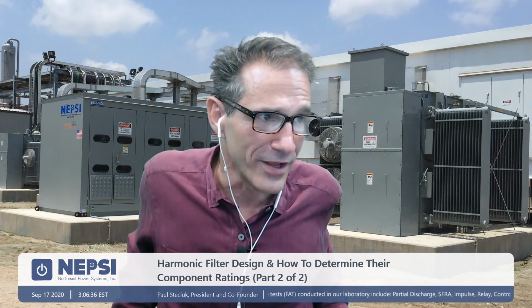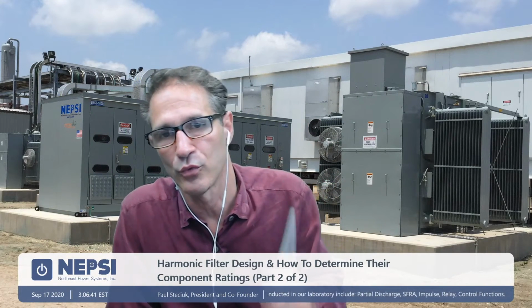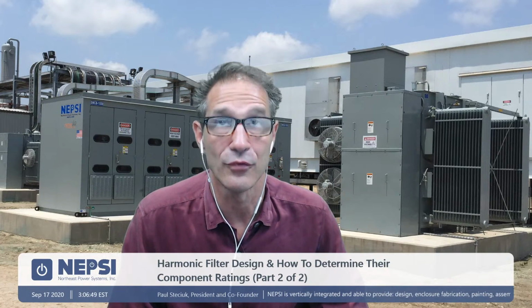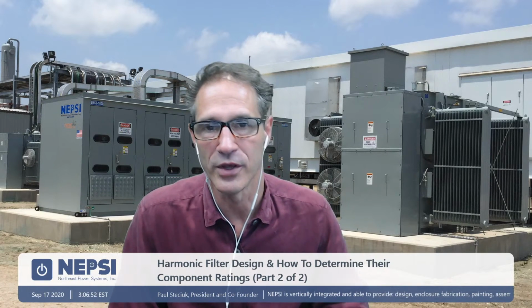So next week we're going to be talking about sweep frequency resonance analysis of harmonic filters. So SFRA testing, not of iron core, but of harmonic filters. We have a large harmonic filter system in our factory floor, and part of our QA at the end, during the FAT testing, we would do an SFRA test on our harmonic filters, basically to verify the characteristic shape of the harmonic filter. We know the shape from our harmonic analysis, from our simulations. We know how it should look.